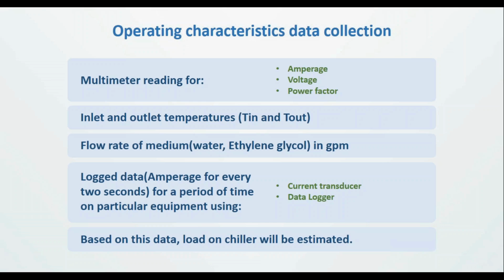And the COP of the chiller can be estimated, and based on the COP understanding and the part load profile, we can arrive at a reasonable conclusion on how much energy can be saved by improving the load characteristics of the chiller. So the data logging is an important part of it, and the more continuous it can be done on chiller systems, the better off we are in trying to understand its behavior with respect to parameters such as production changes, weather changes, and other kinds of aspects that will affect the performance of the chiller. Next.